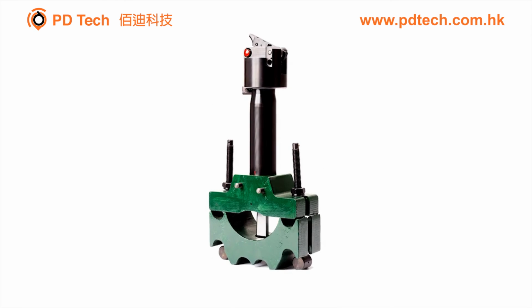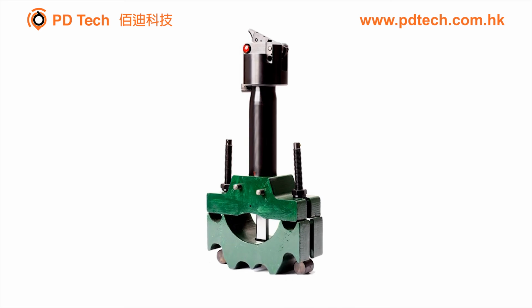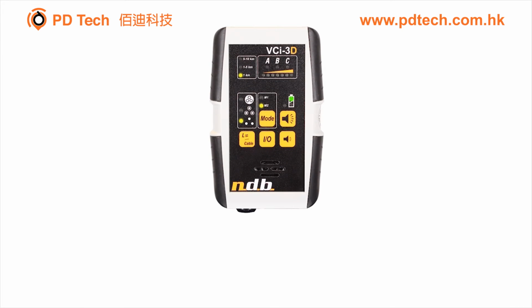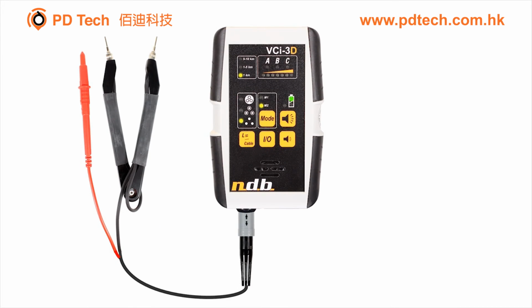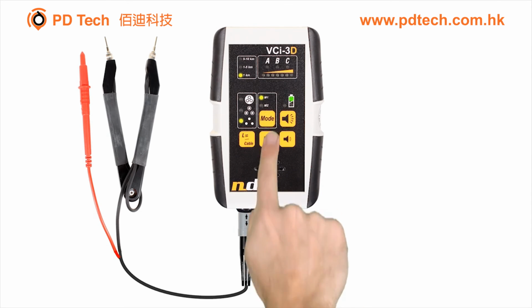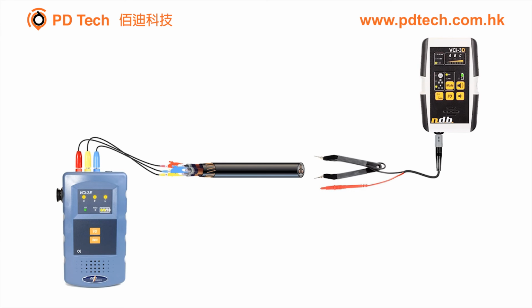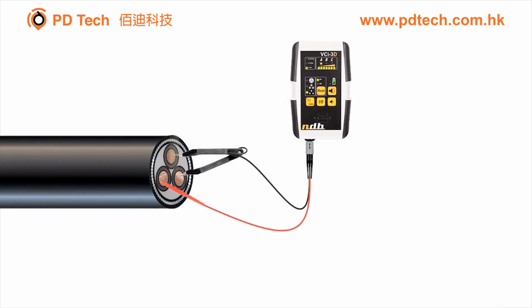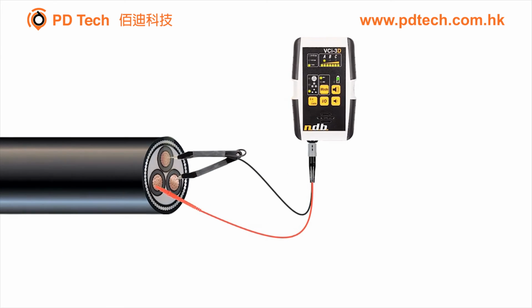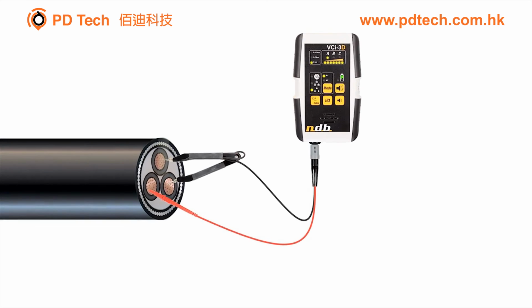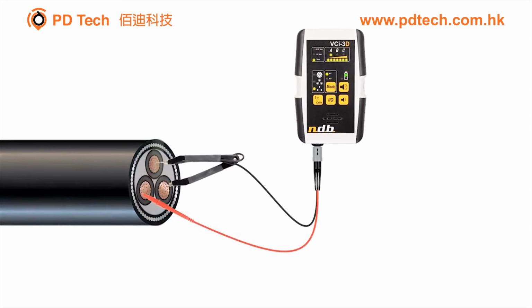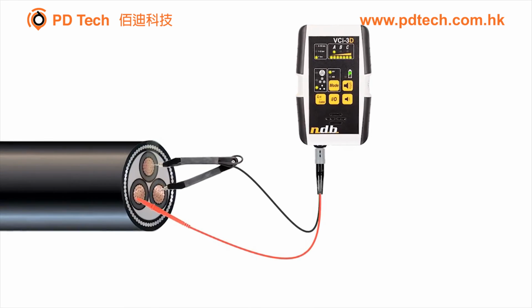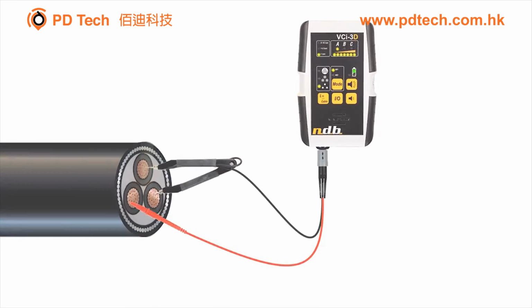Please note the VCI-3 system does not replace spiking the cable prior to splicing. Once the cable is cut, the VCI compass type sensor is used to perform phase identification. For this application, Mode 1 must be selected. Apply the 2 black leads of the compass probe on 2 conductors. Then place the third red lead to the remaining conductor. The detector will display the phase identification for the cable on which the red terminal is applied to. Try all 3 positions for the complete circuit phase identification.